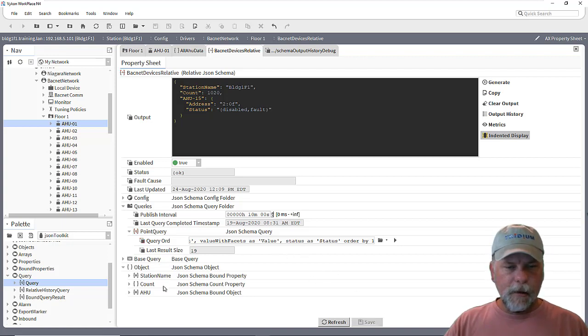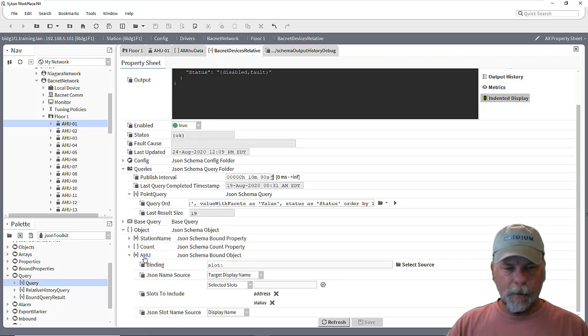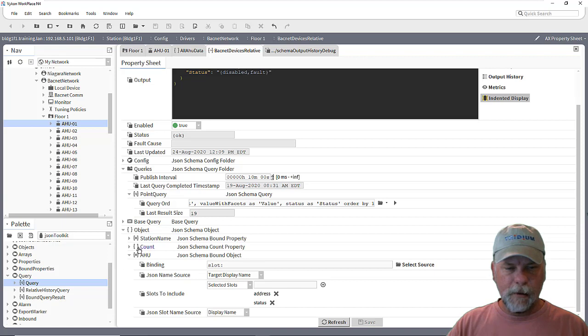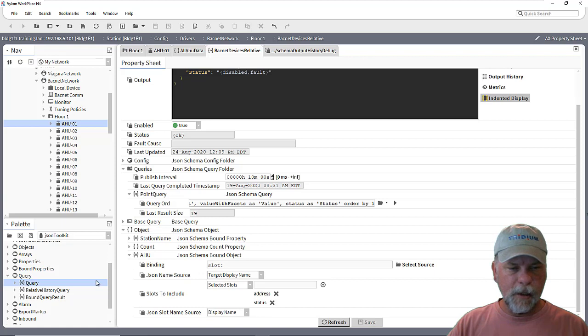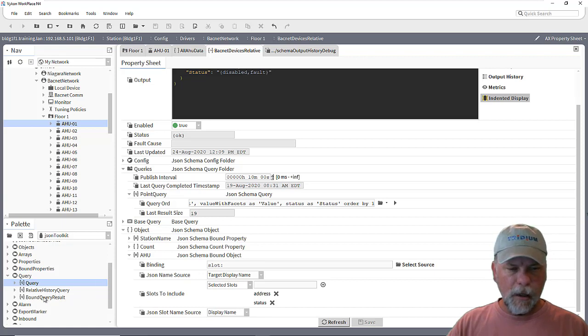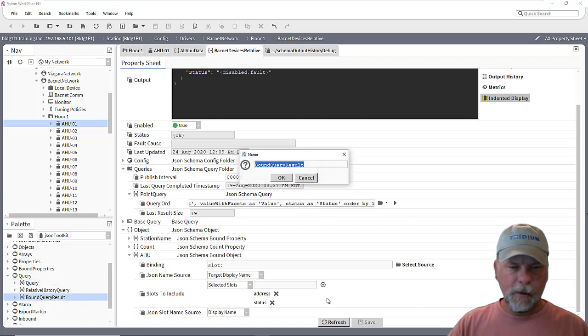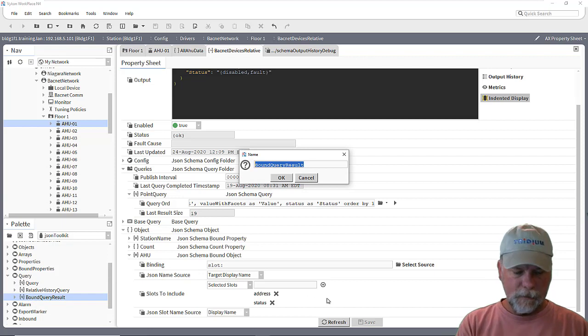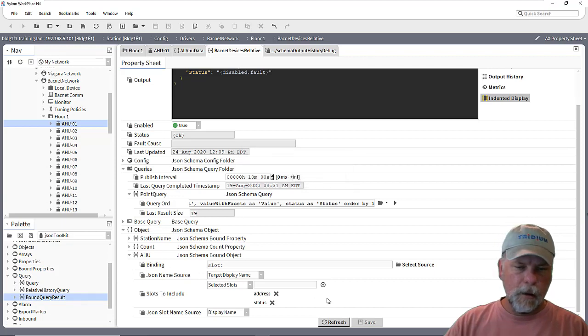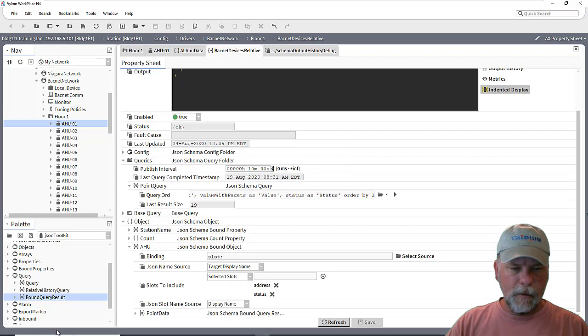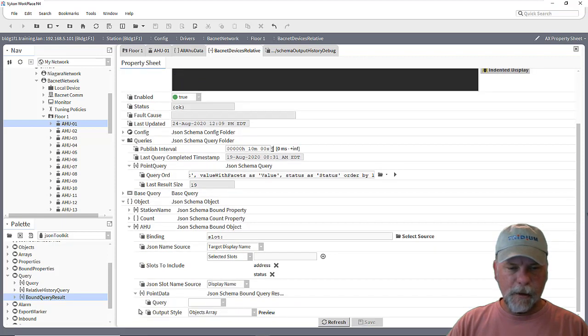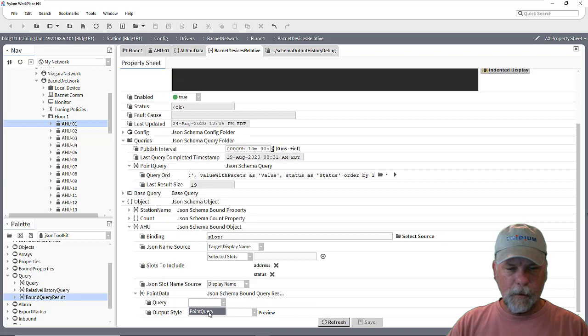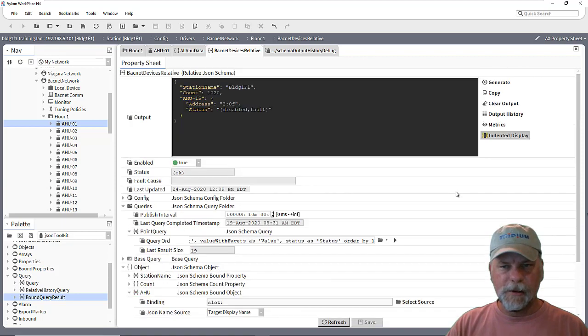And then under the schema here where I'm including the station name, the count, and then information about the AHU like the address and the status and the display name of it and so forth. Then we can drop in a bound query result here and point data. And then we just need to select the query here for the point query and the style that we want to see displayed.